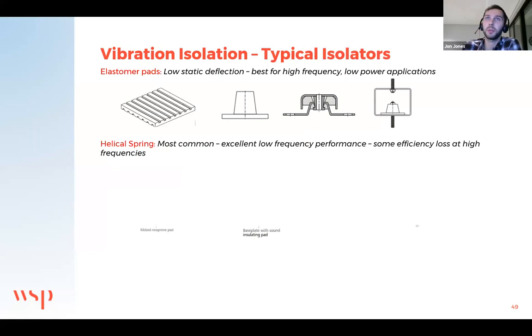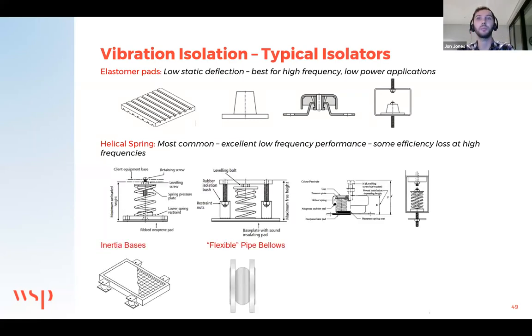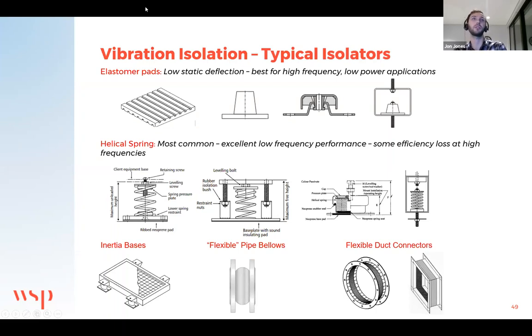A few typical isolators which we can look at installing, which are probably familiar to you. So elastomeric pads, neoprene turrets, these are pretty basic and often used to mount equipment on. These are good at some high frequency absorption. They're not necessarily very intrusive or costly, and they do provide a degree of isolation, which is great. They can be used in hanger forms as restrained turrets, or just as pads themselves. Moving on from pads is spring isolation, which is the next step up generally, and performs better, particularly at low frequency.